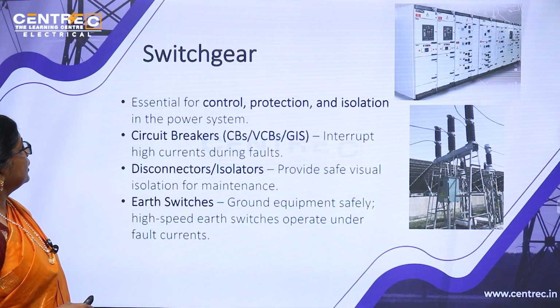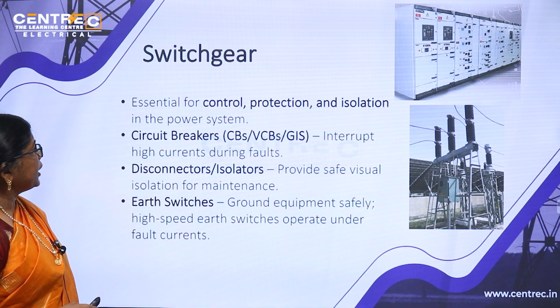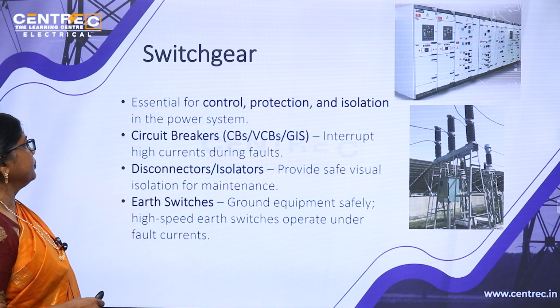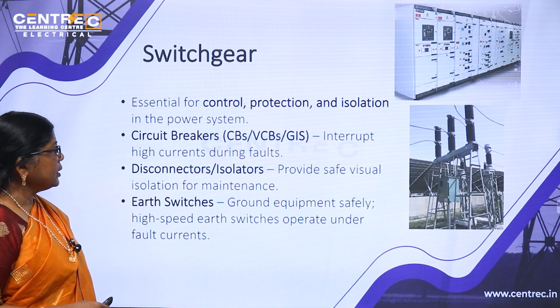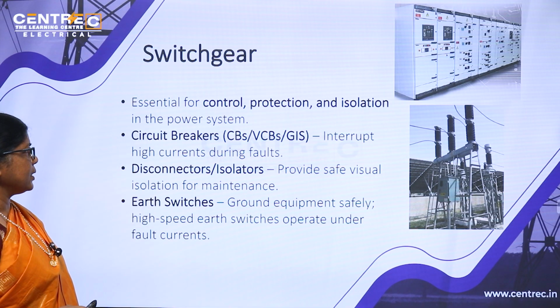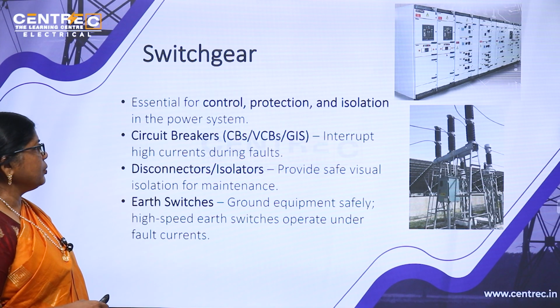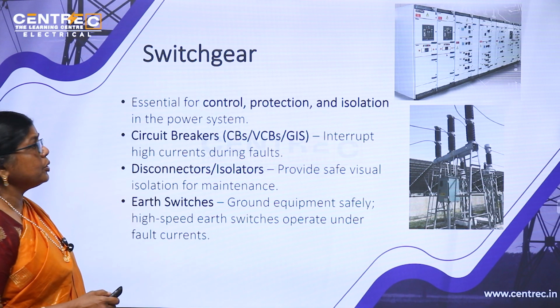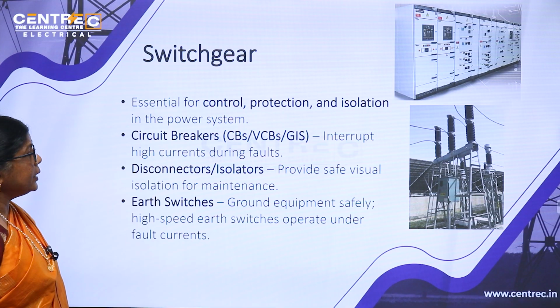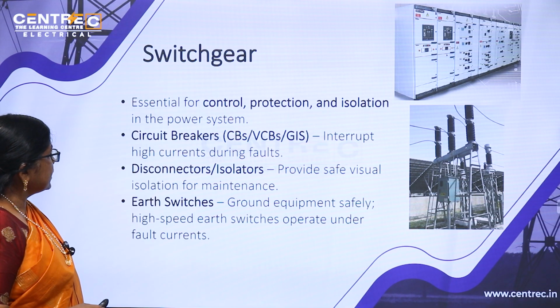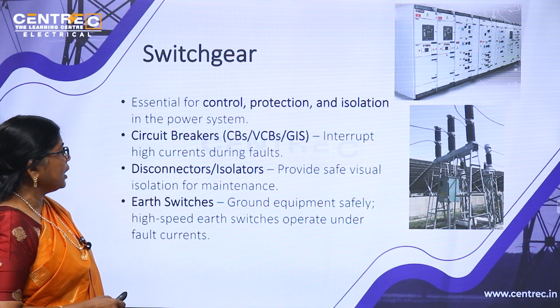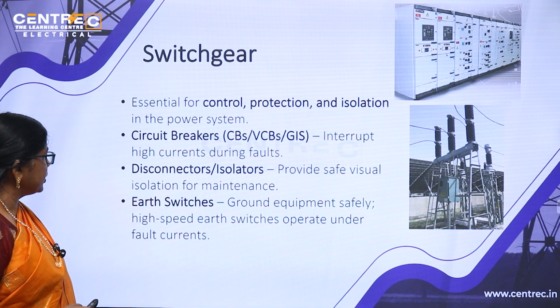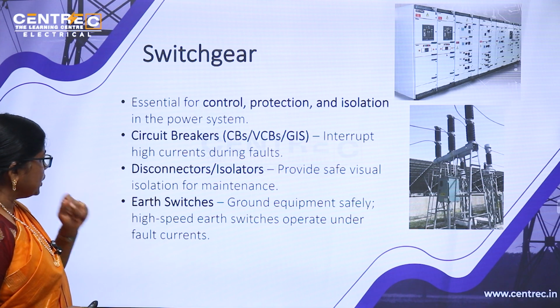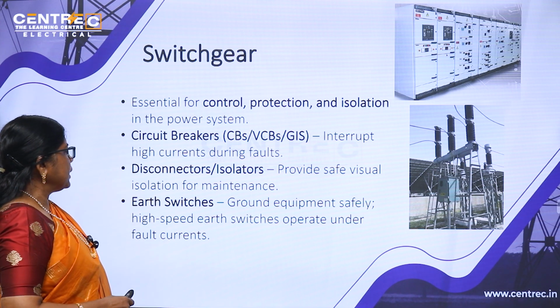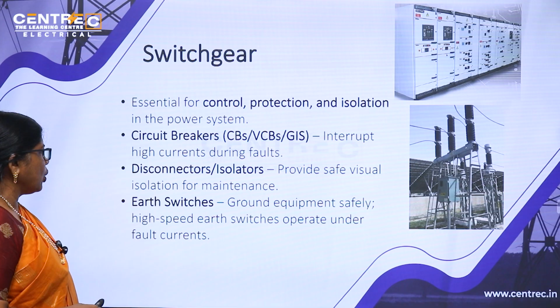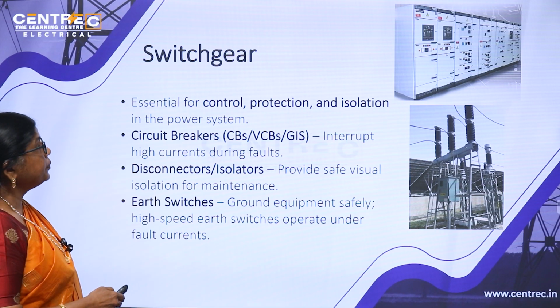Switchgear, essential for control, protection and isolation in the power system. Then circuit breakers, CBs, VCBs, GIS. VCB is vacuum circuit breaker, or gas insulated, which interrupts high current during faults. Then disconnectors or isolators provide safe visual isolation for maintenance. Earth switches ground equipment safely. High speed earth switches operate under fault condition.